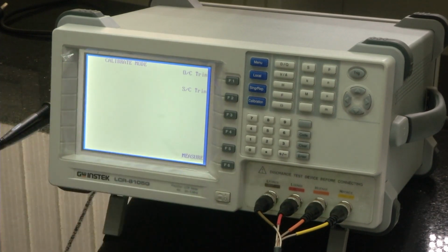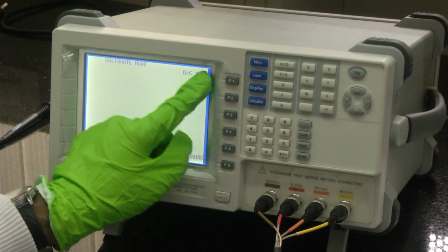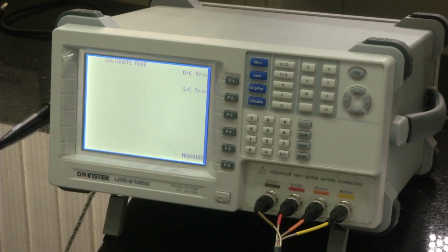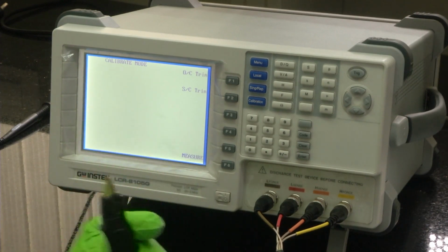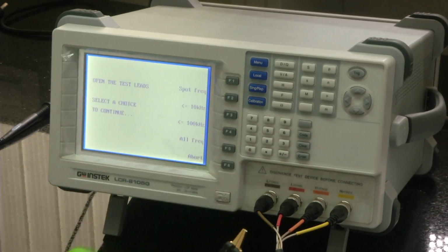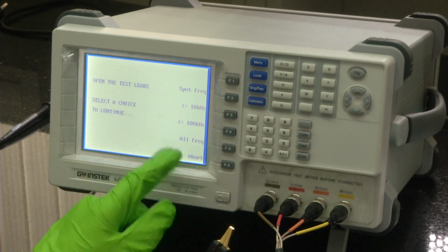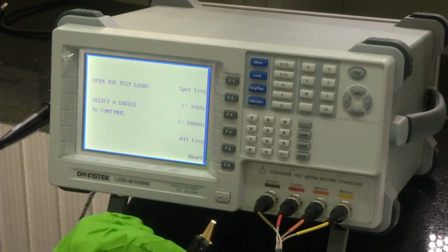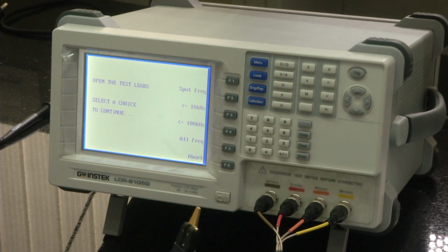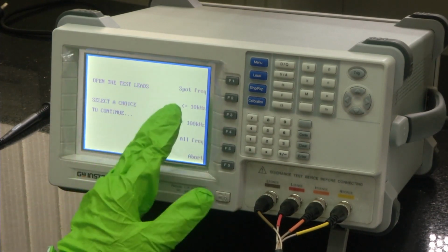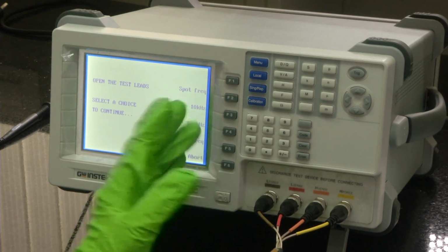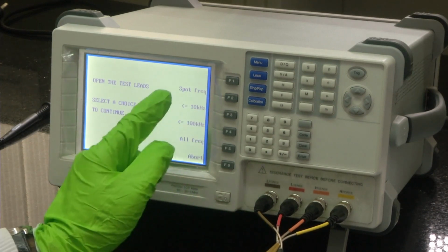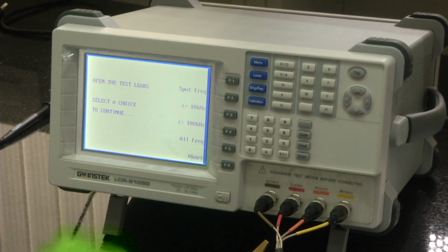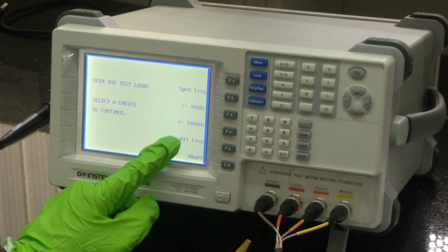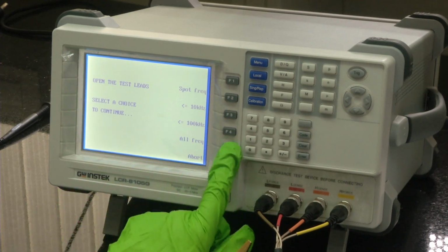There are two types of calibration that we have to carry out, called open circuit calibration and short circuit calibration. In open circuit calibration, we have to keep the probes open, they are not in contact. So, let us do open circuit calibration. Once we click open circuit calibration, the device will ask to what all frequencies you want to do the calibration, because maybe our application might be limited to a particular frequency only. We might be interested in only maybe less than 10 kilohertz, or only one particular frequency, or less than 100 kilohertz. Generally, let us do the calibration for all frequencies. So, I will select all frequencies now.